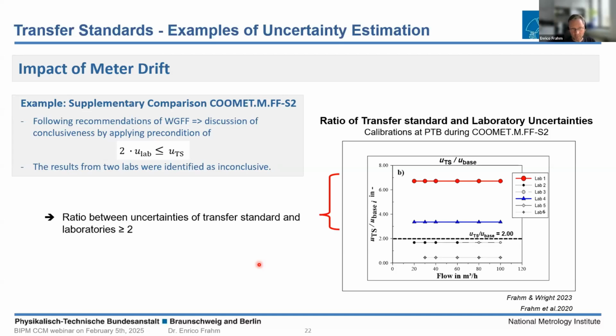It's important to note that the labs passed the EN criterion, but during the discussion of conclusiveness, it was decided that the meter was not suitable. So this is important to separate between EN criterion and discussion on conclusive or inconclusive. So this example demonstrates very clearly that not every transfer standard is suitable for labs with low uncertainties. So basically, the lower the lab uncertainty to be confirmed, the better the transfer standard must be. So in this sense, very simple example. No one would use a domestic water meter to compare national flow standards. So why not? Due to the large meter uncertainty in contrast to the low lab uncertainties. So this is just the basic thinking behind this point.